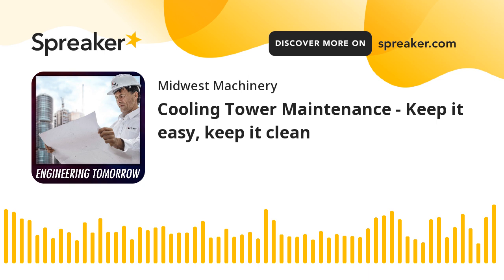But Stephen, let's open it up with the most basic question: what is a cooling tower? Wow, we're already starting off with a pretty tricky question. In the simplest terms, a cooling tower takes water and lowers its temperature by running it over a fill material, with a fan pushing air through it as the water trickles down. It's really just to lower the water temperature. Ideally, you'll get a 10-degree delta T.